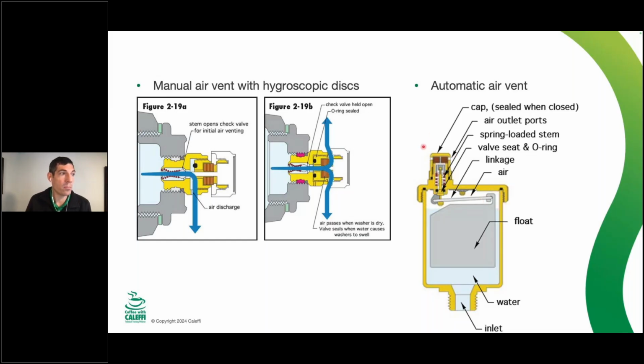What I have done before is taken a little control screwdriver and pushed down that needle vent until all the air comes out and I get a little splash of water out the top, and I think, okay, that's great. We got all the air out. I actually don't want to do that, because this little air pocket here is a good buffer to keep the Teflon tape and a wood chip or whatever may float up to the top, little pieces of plastic or something like that, from coming in contact with an air vent.